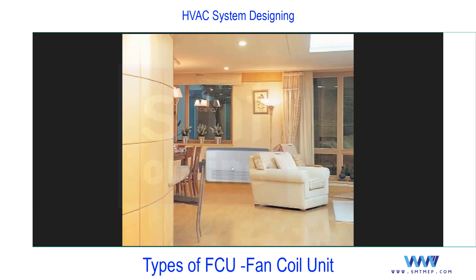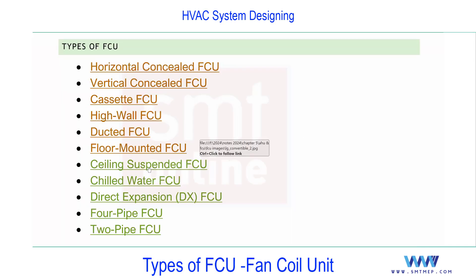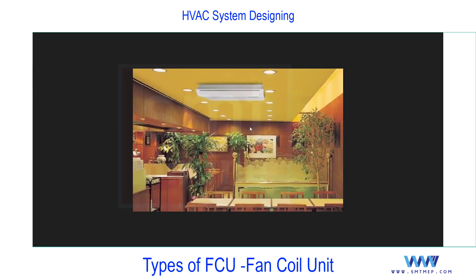The floor-mounted decorative FCU is a rare option with very few models available. Technically it is not recommended for cooling because cool air is dense and tends to stay low, providing poor distribution. However, for heating it is a good option since hot air is less dense and rises, effectively heating the room. It is available in the market but not commonly used.